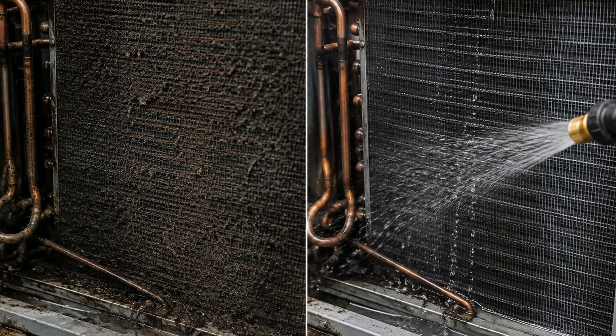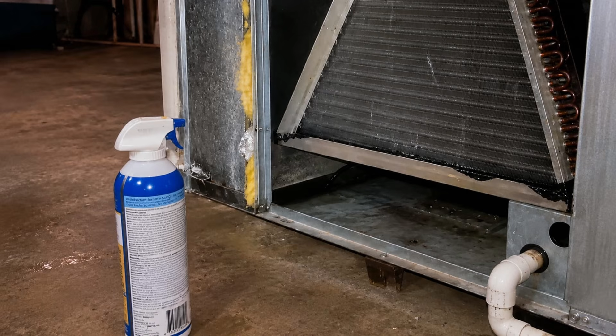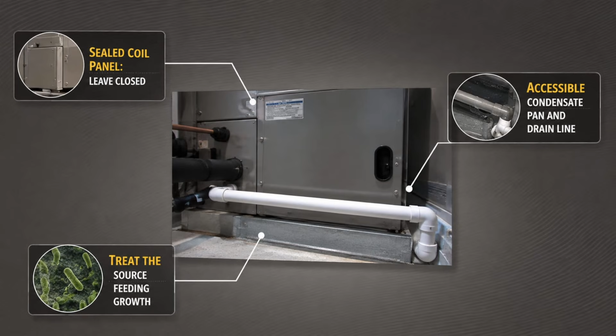One honest limit: peroxide kills the living layer, but it won't dissolve the greasy bonded gunk that also cakes a badly neglected coil, which needs a real foaming coil cleaner. And if your coil is behind a sealed panel, leave it shut and treat the pan and drain line underneath, because that's what's feeding the growth anyway.